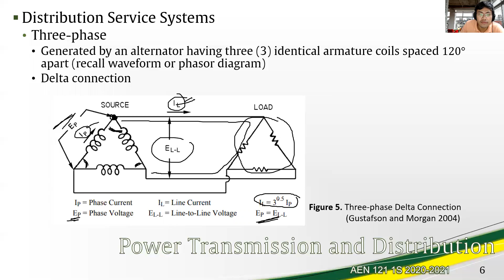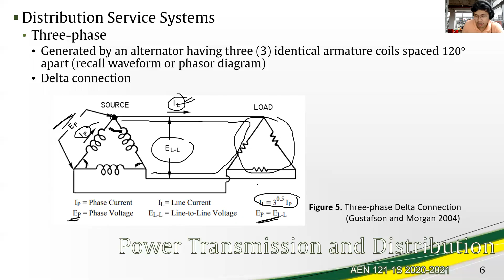the line-to-line voltage equals the phase voltage. Now the IL, if you compute that based on the 120 degree difference, you get it as 3 raised to 0.5, or the square root of 3 times IP. That is the relationship if you are using a delta connection.